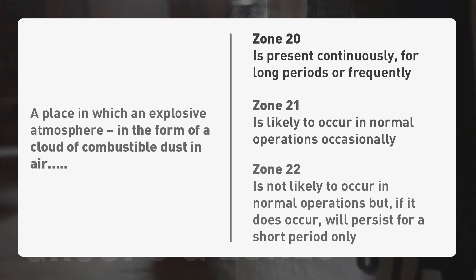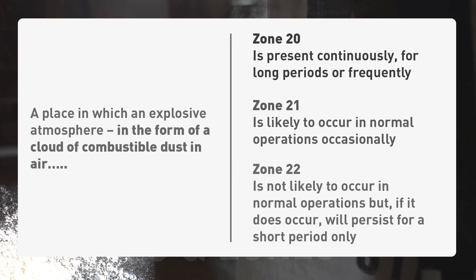If the potential explosive environment is from the risk of a cloud of combustible dust in the air, the class of the ATEX zone would be identified either as zone 20, zone 21, or zone 22. The classification of 20, 21 or 22 would depend upon the considered likelihood that the explosive environment will occur and the frequency of its occurrence. In the case of zone 21, it is considered likely that the explosive environment would occur in normal operation but only occasionally.